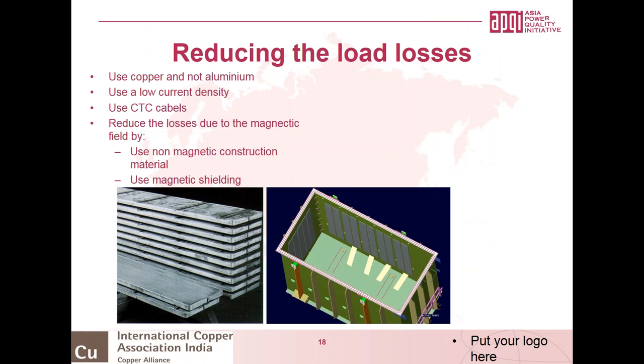Looking at reducing the losses of transformers, the load losses I'm talking about, sorry, the material you can use is still copper, and don't use aluminium in case you have a large transformer, because you will have a larger transformer and it will also have a negative impact on your short circuit forces, because aluminium is not as strong as copper is. Also use a low current density in case you want to reduce your losses. I already told you to use CTC cables, continuous transposed cables, because they will reduce your eddy currents in the windings, and also reduce the losses due to the magnetic field by using magnetic shielding. And that's what I show you on the picture.